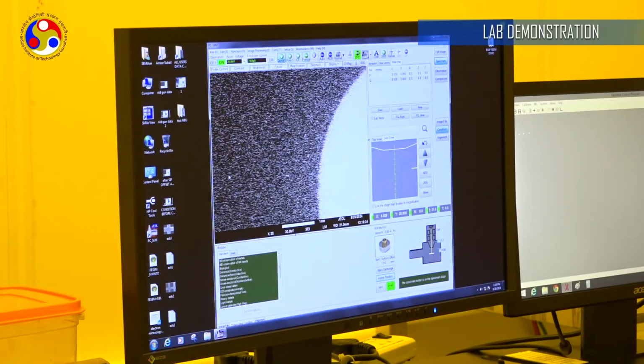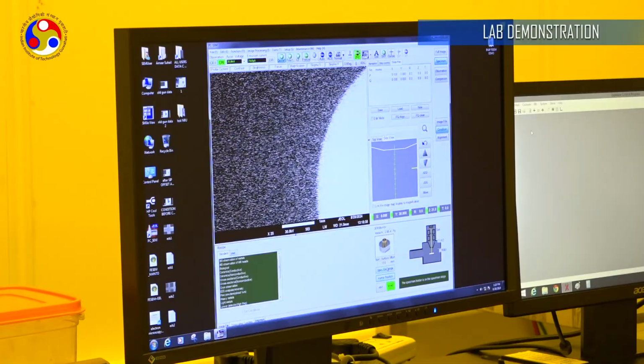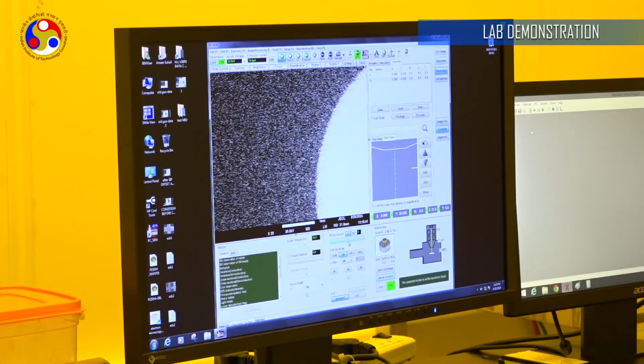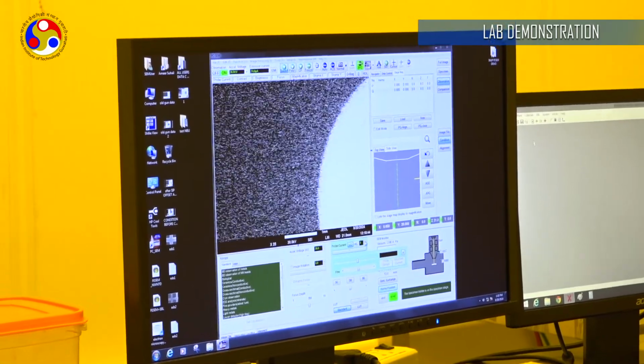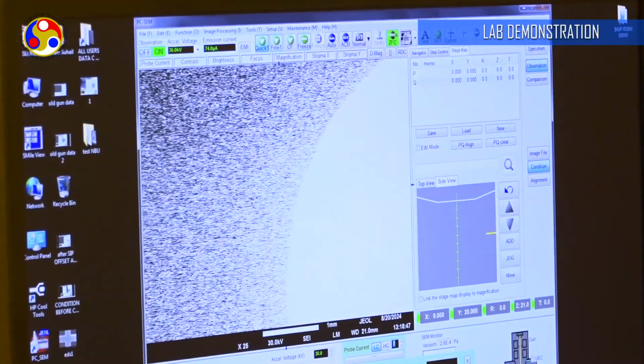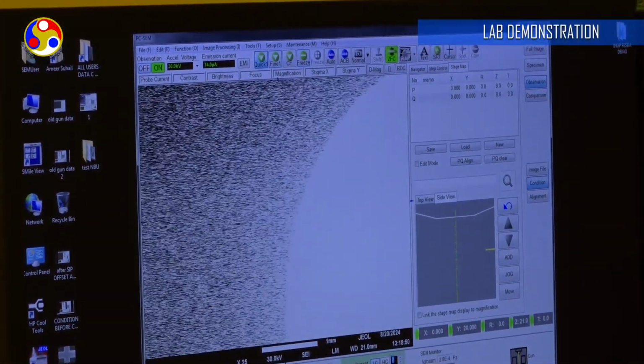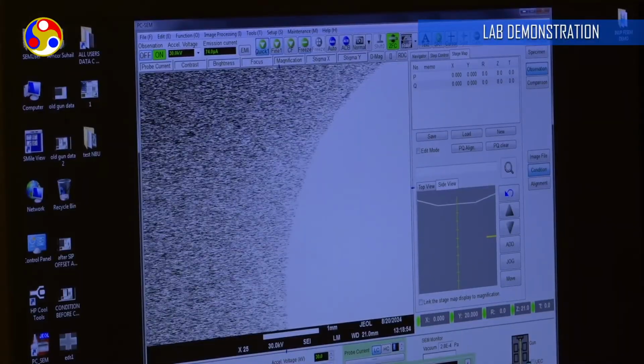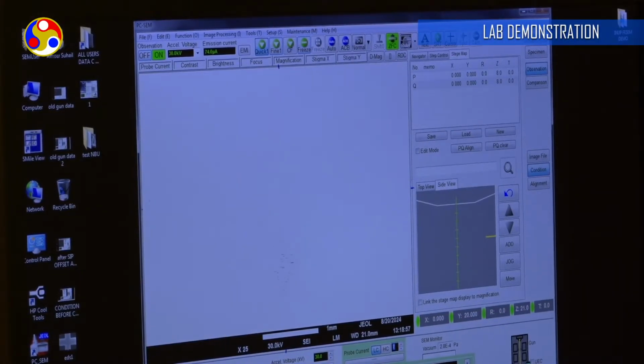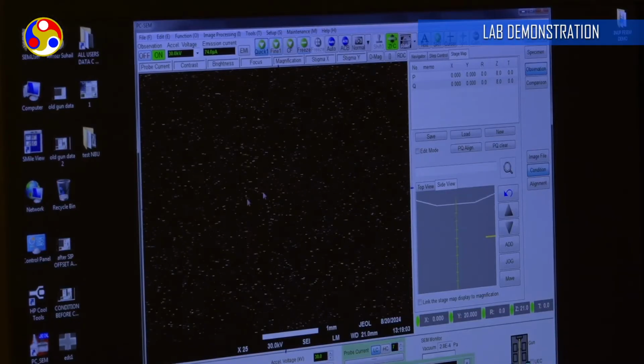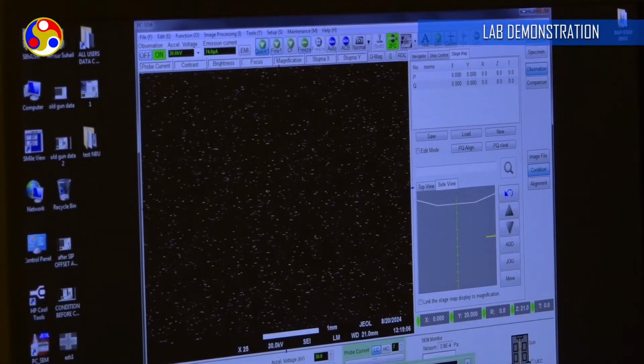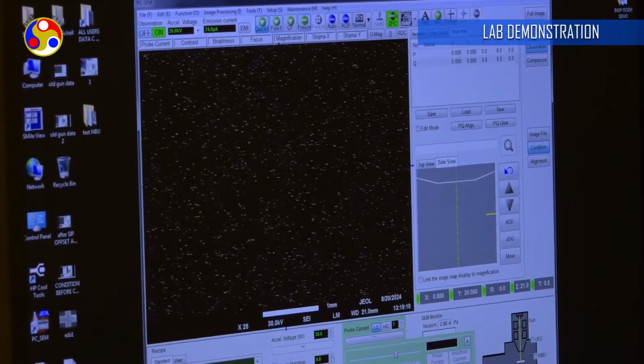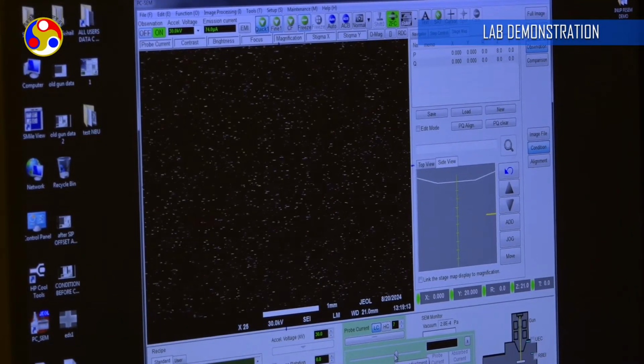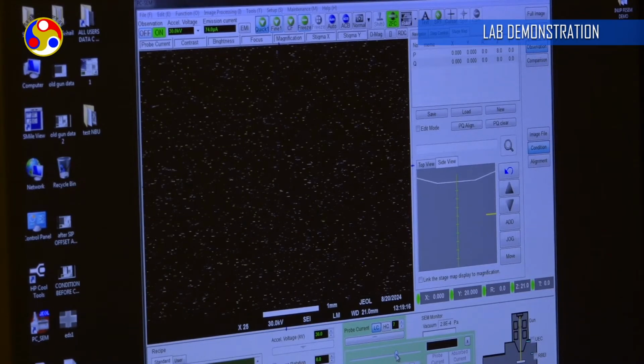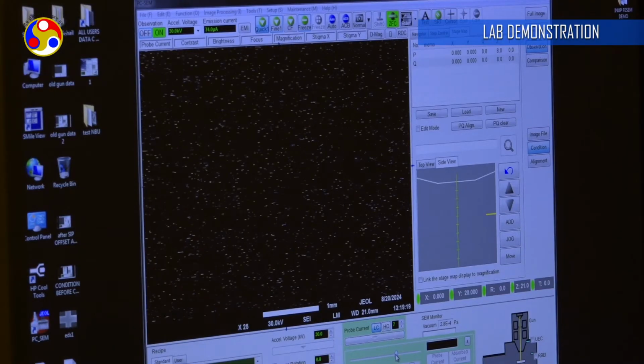In our next step, we need to adjust the probe current. To adjust the probe current, we need to increase the probe current to a value of 7, and in the EBL computer we go to EBL, then beam control, and here beam on. Then we need to click the PCD. Now the image on the screen will vanish, and we need to adjust this current to 100 picoampere. To adjust this, we will vary the probe current here, and we will set it to nearly 100.